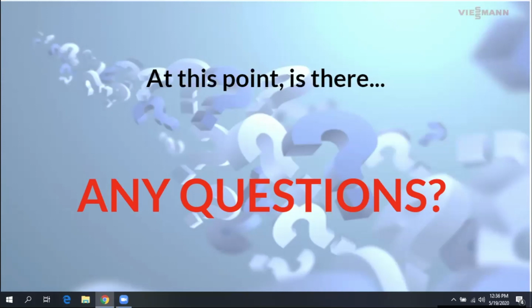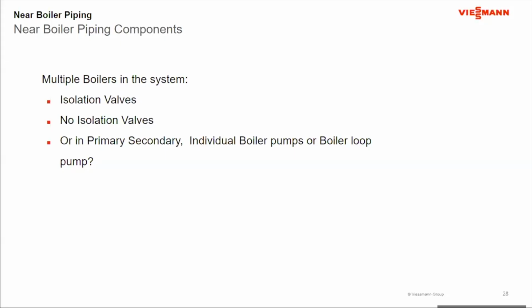Because if I have a system with 2, 3, 4 or more boilers, not every boiler is required to fire at all times. So it becomes a matter of what do I do to isolate, or do I isolate the off-service boilers? Do I use isolation valves? Can I get away without isolation valves? If I'm doing primary, secondary, do I want individual boiler pumps, or do I want a boiler loop pump in primary, secondary? So this is really our next level of discussion.